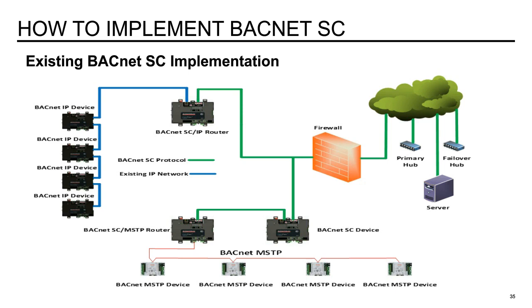Okay. From Daniel, can there be an issue switching over existing networks to BACnet SC with existing BBMDs? No, not as long as you implement the BACnet SC routers and devices and hubs for the networks that you have. You should not have a problem doing that. Okay. From Jared, the question is, you will still need BBMDs in a BACnet SC over IP router, correct? No, you would not. Because once again, BBMDs are typically used to push or manage data across multiple networks. Keep in mind, with a BACnet SC installation, you're segregating your network with a BACnet SC device and hub.